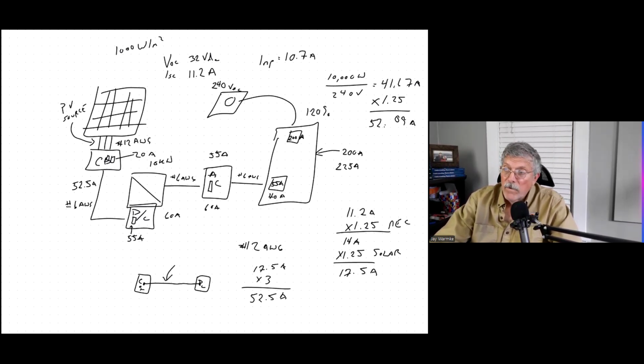If it's already rated for 225, great. No problem. We're fine at the 55 amps. Another option would be to replace the main breaker. Instead of 200 amp service, maybe go 150 amps. But as long as between the two, we don't overdo 120% of the rating of the box, that's all we're worried about. So that's the 120% rule.